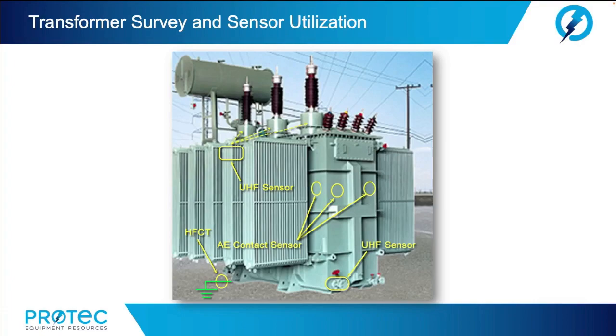For transformers, we can use UHF sensors, scanning and monitoring along bushings for any internal partial discharge. We can also use the parabolic dish and ultrasonic along the bushings for any signs of surface tracking or corona. We can use the AE contact sensors for in-tank testing, and also a UHF adapter sensor for the drainage plugs. Also, we can take HFCT measurements along the ground straps.